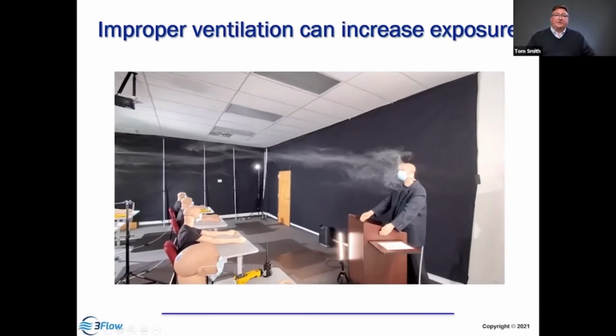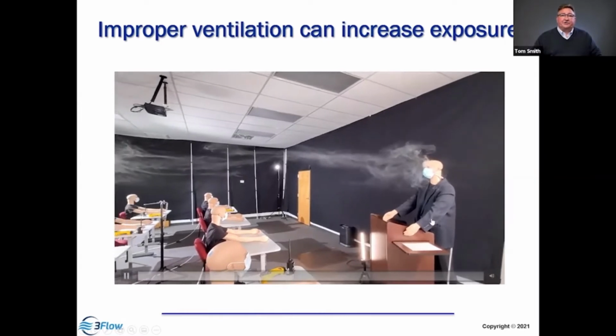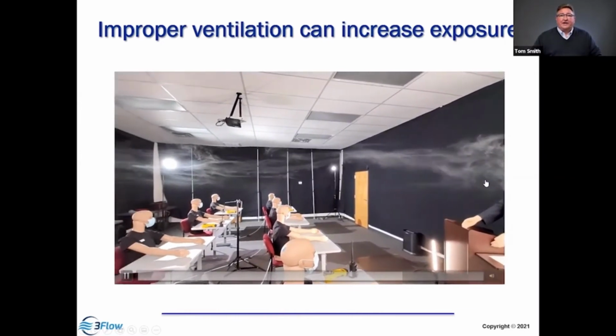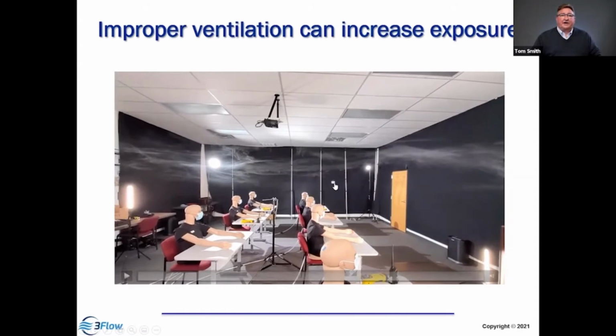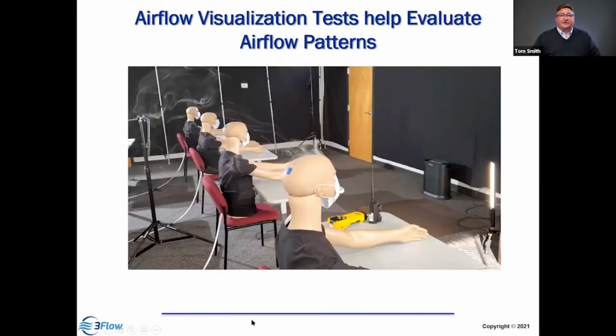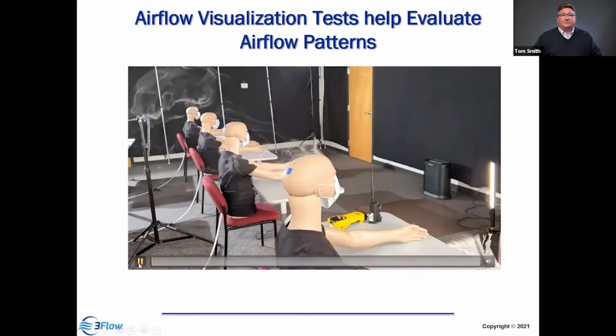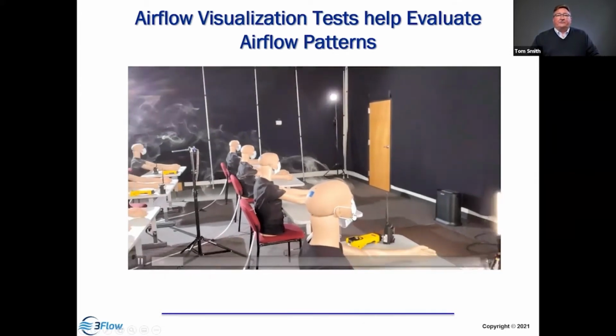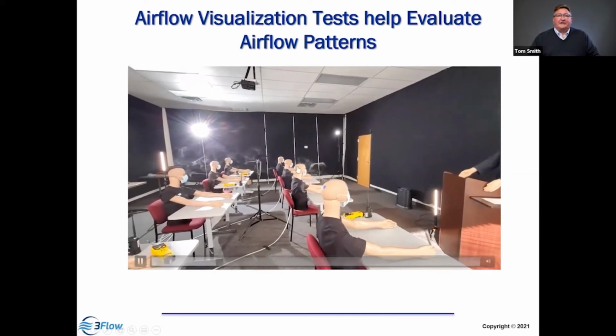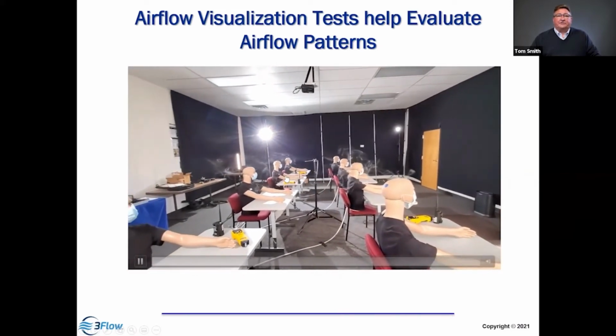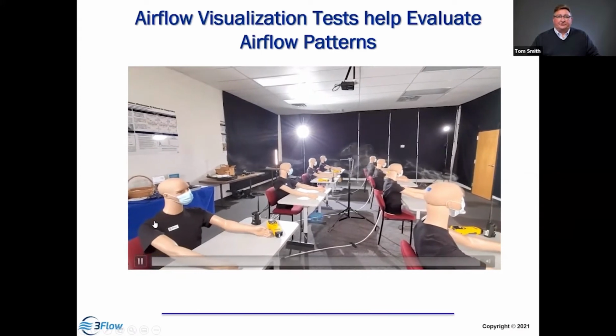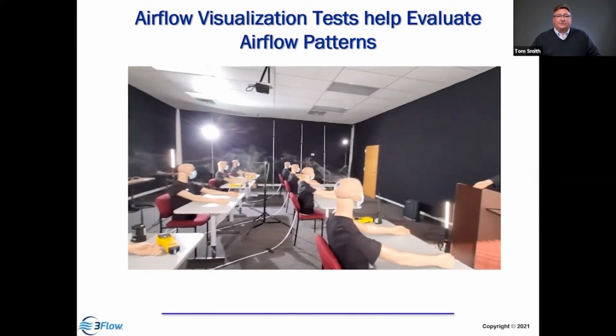So we'll take a look here as our teacher in this particular case is standing at the podium, and we can see the materials migrating throughout the space. And so you can see the stratification, and that shows that it's not well mixed, that we're actually getting some movement of those materials. Let's look at another example. Here this mannequin is exhaling, and as we begin to see the production, the airflow patterns are moving that material back away from this person, but unfortunately, it's moving right toward this person, and now this person's going to get the majority of the exposure.